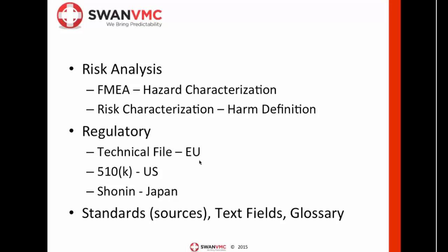Or do you create a link between those standards or sources of the requirement and then create your own product requirement that processes those 4 standards in a way that is appropriate for your device? And that way, the link is direct, but the thing you're standing on is one well-defined requirement. They don't step on each other. It's all been processed, and it's a really slick way to kind of resolve conflicts of standards, because sometimes one will say one thing and something else will say something different.